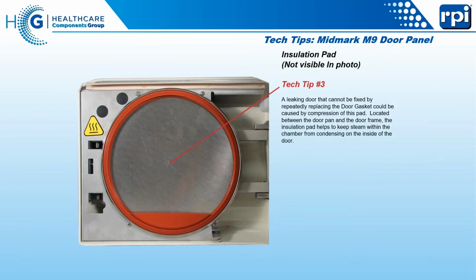There are a couple of things you can do to tease that information out without actually pulling it out. If a customer says they put a door gasket in and it's just not working right, the first thing you can do is take the door gasket out and rotate it 90 degrees to see if it's worn differentially because of this problem. If that seals it up, okay, we're getting suspicious about that pad.